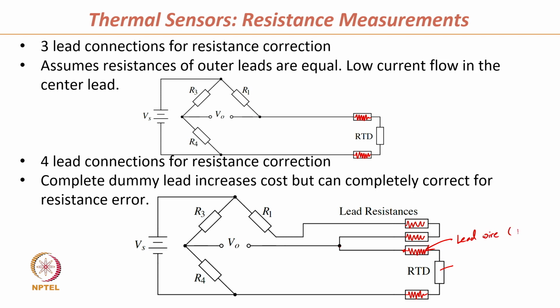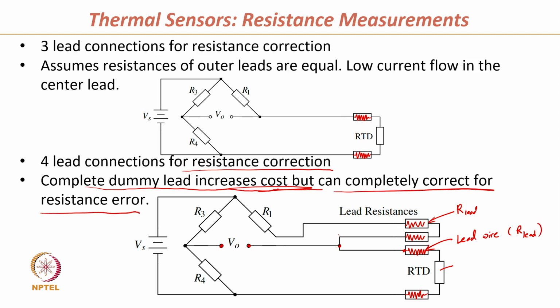Let us say this is our lead wire, our lead. So, these are also our lead which we connect on the other arm of Wheatstone bridge to remove this error, and we take measurement between these 2 points. So, this is 4 lead connections for resistance correction, and we put dummy lead wires in the measurement to reduce the error, but it increases some cost because of these extra wires, and we can completely correct for this resistance error using this Wheatstone bridge.